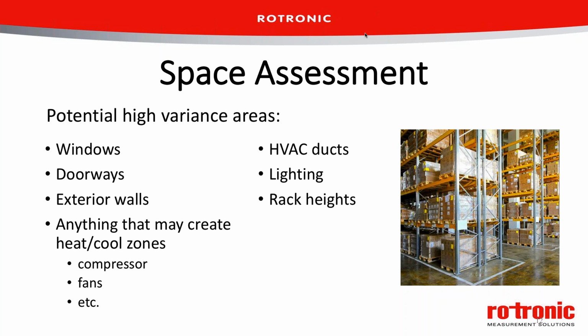And this can also affect the protocols a lot, because you'll need to identify these areas of concern. And of course, if you can do that ahead of time, it also helps to limit the protocol revisions. The heat affected areas can affect the number of sensors required, and it may alter the expectations of the mapping. So you should consider these things, and even consider moving items to other areas or making changes to the facility before you begin the mapping.